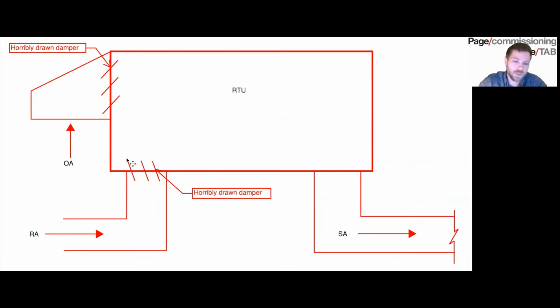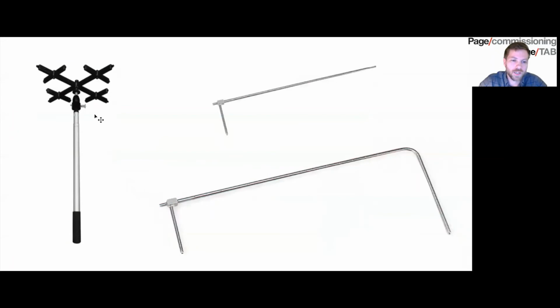Now, there are situations where you get some leakage through the return air damper. So you can go to the beginning of your return, use some plastic and cover it up so that you get no airflow through there. Just make sure when you're doing this that your airflow has already been backed down and your outside air damper is open.